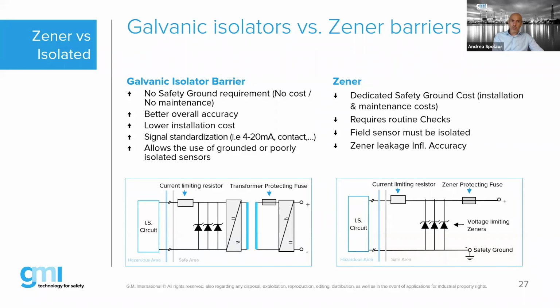It's used for signal standardization, so 4 to 20 milliamps, contact or temperature, whatever. As we said, you can use any kind of sensor without thinking, without checking if there is an isolation of 500 volts for the hazardous area. While the Zener needs dedicated safety ground, costs require continuous checks, field sensor must be isolated, and there is leakage.